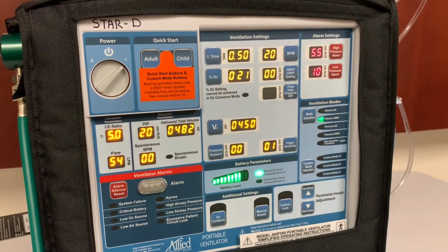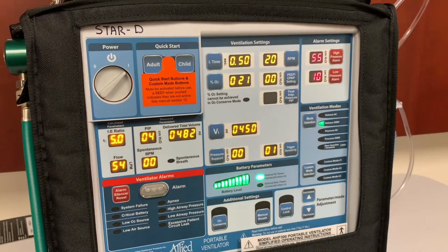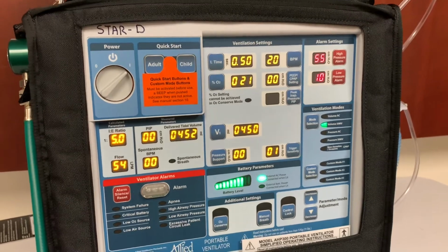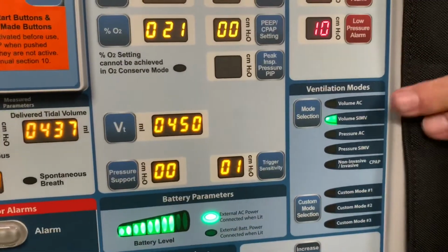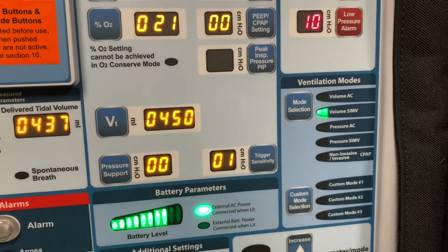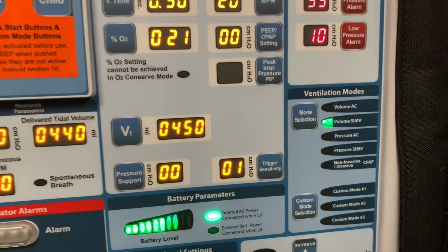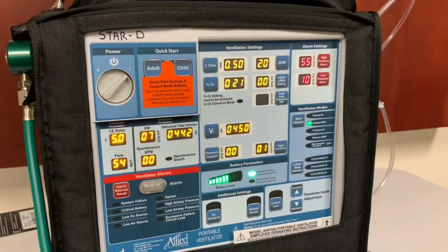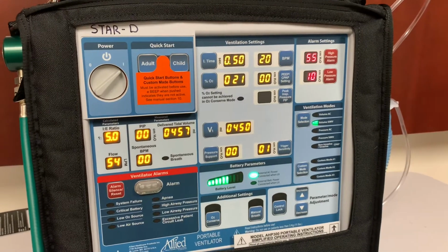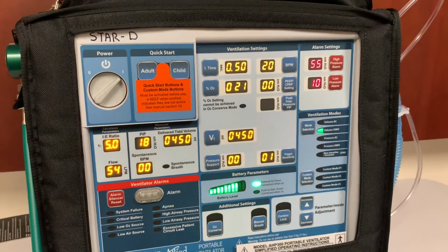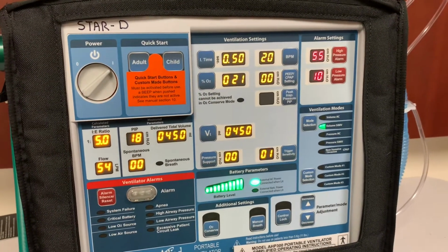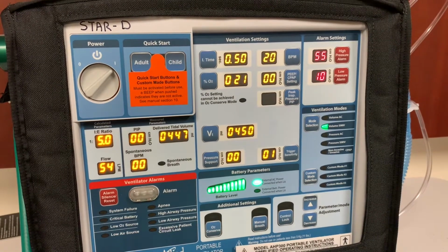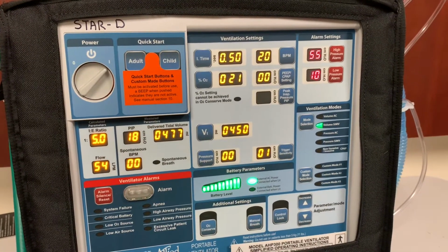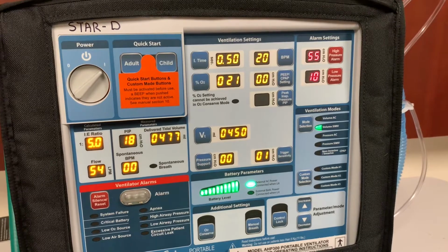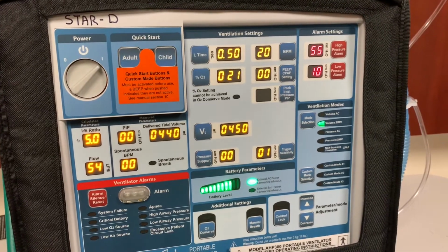The ventilation mode that we're going to choose for the standard adult intubated patient is going to be the volume SIMV mode, which stands for Synchronized Intermittent Mandatory Ventilation. In this mode, it will deliver the set tidal volume at the set breaths per minute to the patient. However, it will adjust for when a patient takes a spontaneous breath and will adjust its timing accordingly as to when it delivers its next breath.